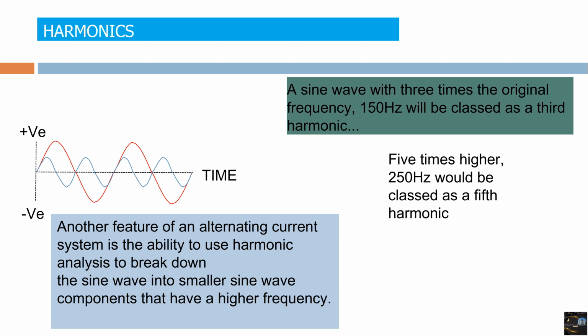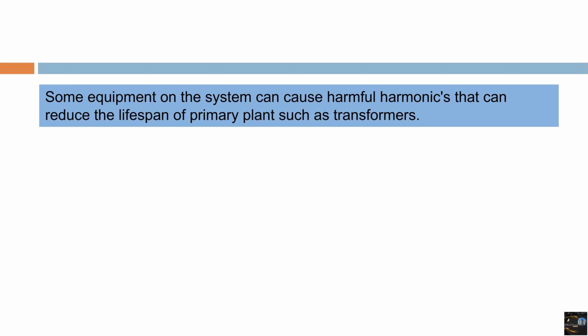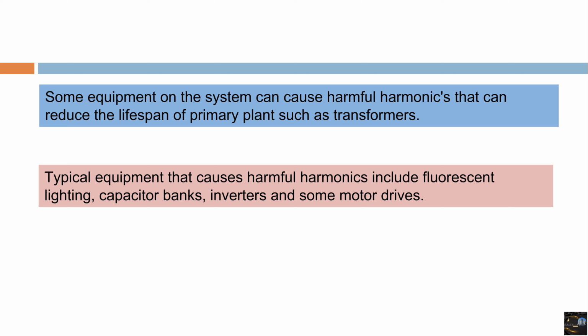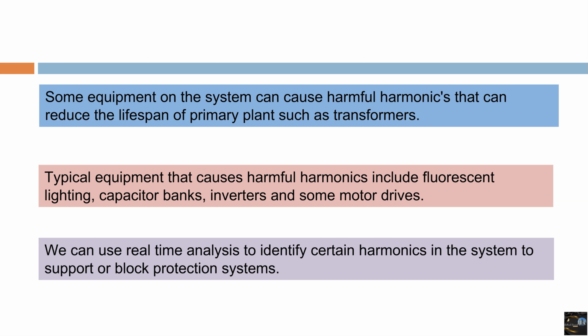Some equipment on the system can cause harmful harmonics that can reduce the lifespan of the primary plant, such as transformers. Typical equipment that causes harmful harmonics includes fluorescent lighting, capacitor banks, inverters, and some motor drives. In my other lectures, I will show how we can get rid of harmonics from the motor drives or the inverters in some separate lectures. We can use real-time analysis to identify certain harmonics in the system to support or block protection systems.